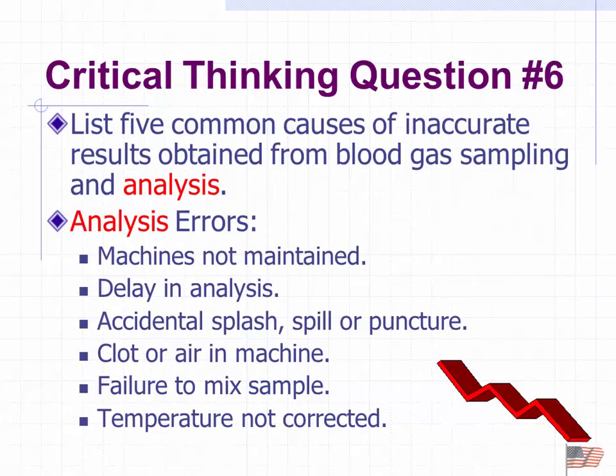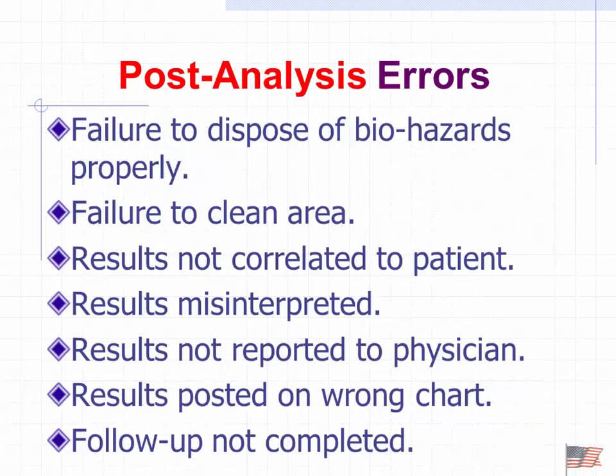Well, there's lots of errors that can happen during the analysis. I've got a machine that's not being cared for properly. It's not being maintained. It's garbage in, garbage out. Delay in analysis we talked about. If the sample is left to sit on the counter, within that sample there's white blood cells. Those white blood cells consume oxygen, produce CO2. It's going to skew the values there. Splashes or spills, clots, not mixing it well, not accounting for temperature.